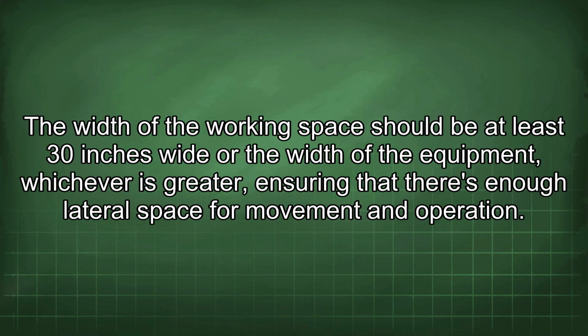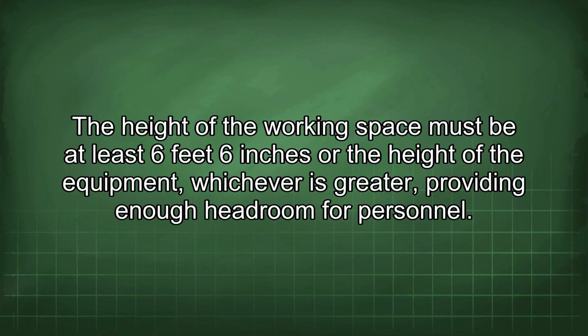hazards. The width of the working space should be at least 30 inches wide, or the width of the equipment, whichever is greater, ensuring that there's enough lateral space for movement and operation. The height of the working space must be at least 6 feet 6 inches, or the height of the equipment, whichever is greater, providing enough headroom for personnel.